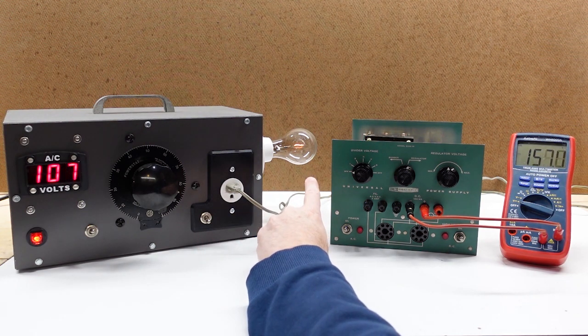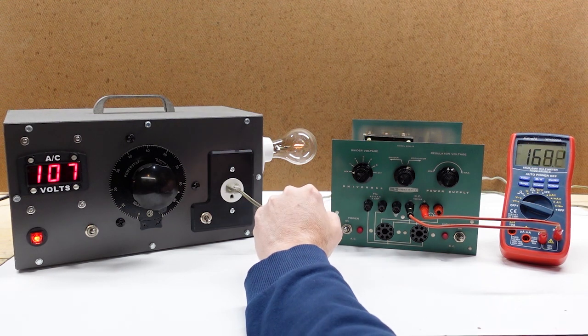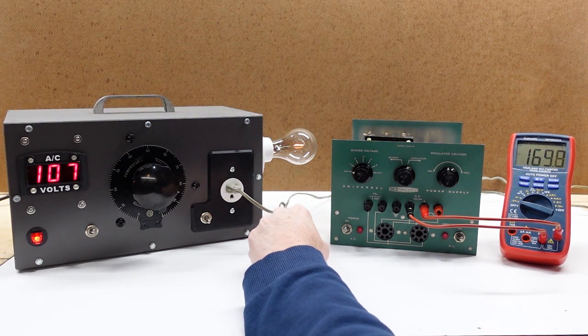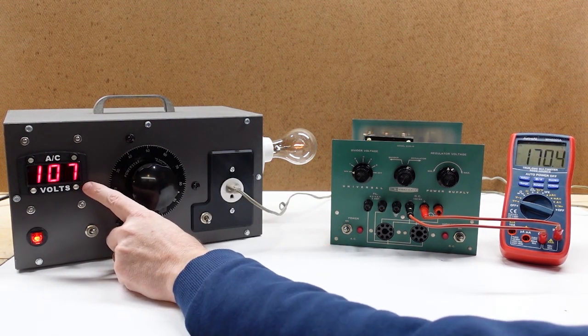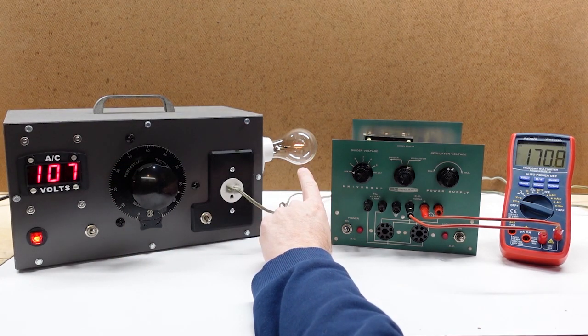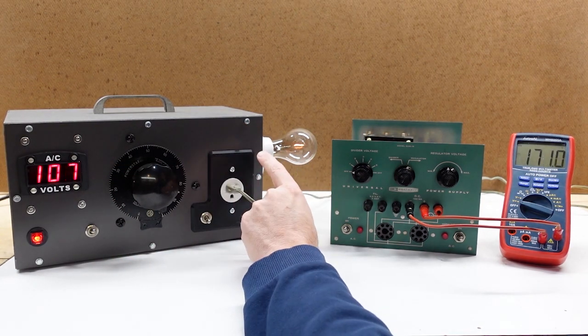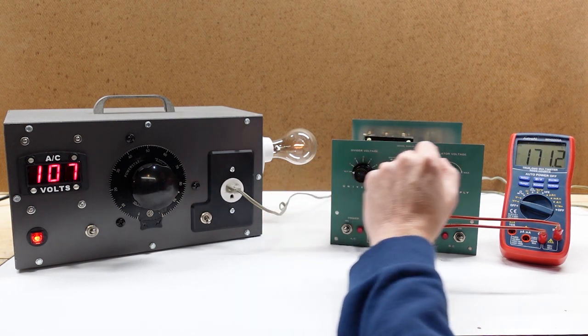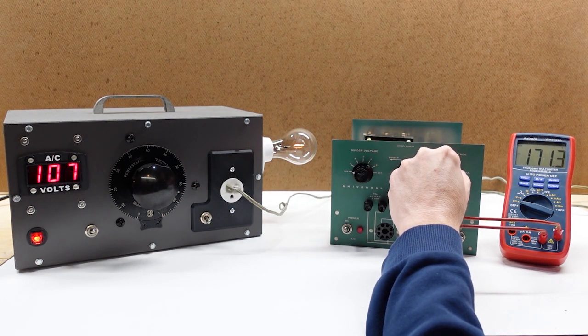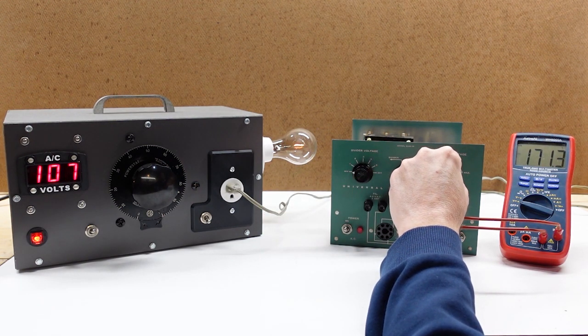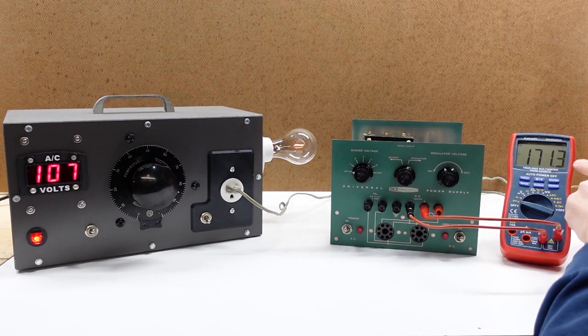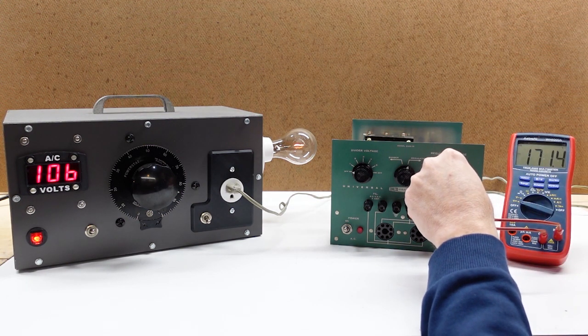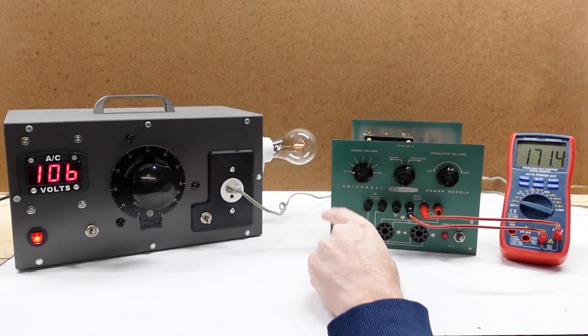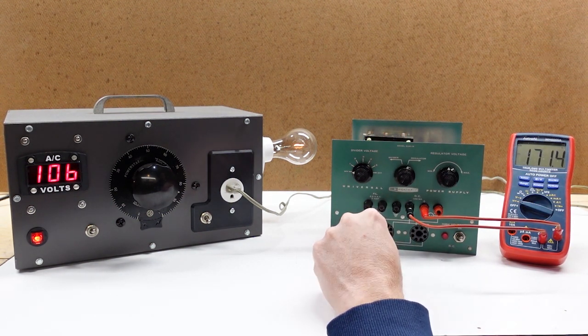The bulb is glowing dimly. That's a good sign. I see the filaments glowing again in the vacuum tubes. That's another good sign. Now I am a little low here on voltage, and of course there's some voltage drop from the bulb adding to that. So nevertheless, let's see what's happening here. Now that's a concern. That number should be changing as I'm altering the regulator voltage setting. So I may not have enough supply voltage to the power supply.